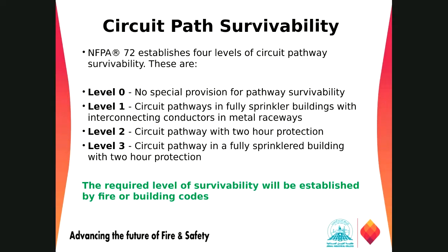You can see that level 0 has no provision for any kind of survivability, so it may get damaged. Level 1 means this circuit is in a sprinkler building, fully sprinkled with a fire sprinkler system, and the conductor is in a metal raceway. So it will be level 1 until the metal gets heat and melts. Your circuit is protected, right?